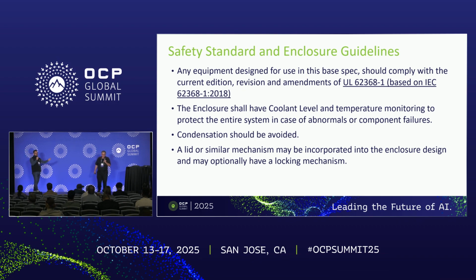There are other things we've taken from immersion requirements, and things we're learning from ASHRAE and other institutions. We've been defining into the spec some of the things considered by the community. For example, one is the coolant level we need to monitor in the tank to protect against short circuits or component failures that aren't being cooled, which can create a fire situation.